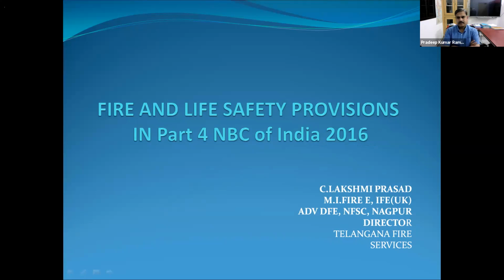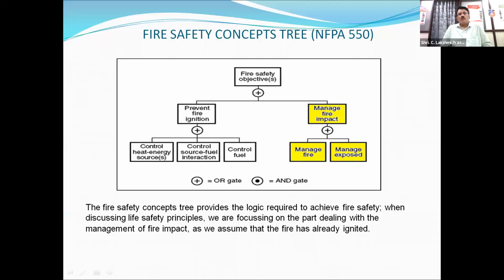Yes. Now we are actually talking about Part 4 of the National Building Code of India, which deals with fire and life safety provisions. Then the fire safety concepts tree, as given by the National Fire Protection Association of US. They are the pioneers in the field of fire engineering, and as per this, what are the objectives of fire safety? First is to prevent fire ignition. That is the most important thing. And if at all prevention is not possible, when fire happens, then we have to manage fire impact. In preventing fire ignition, there are control of heat energy sources, control of fuel, and control of fuel interaction. Fire is a combination of major things like fuel, ignition, air, and also chain reaction. That is called the fire tetrahedron.